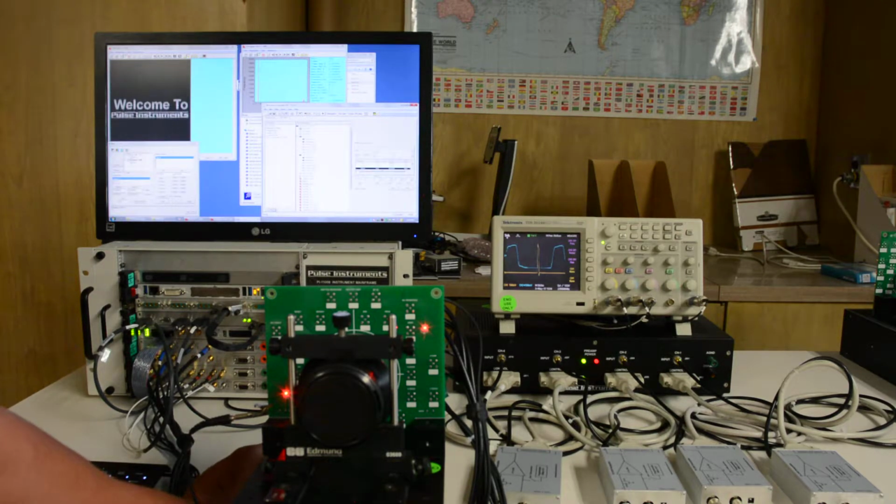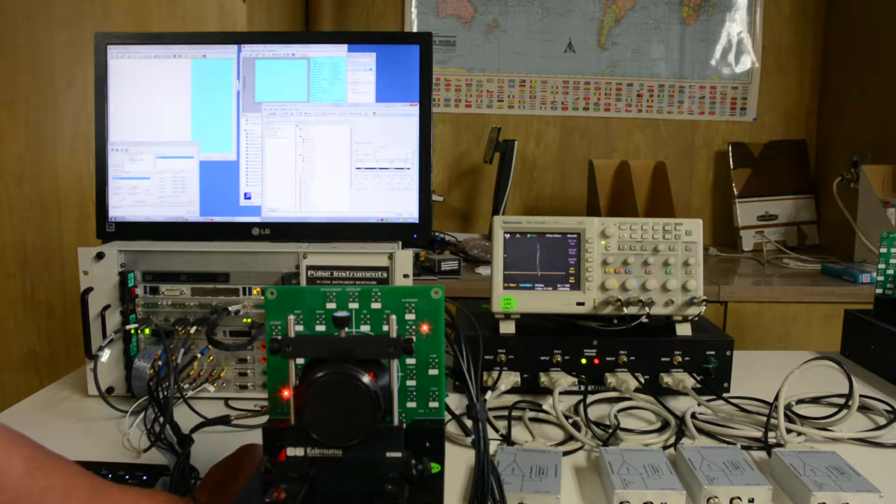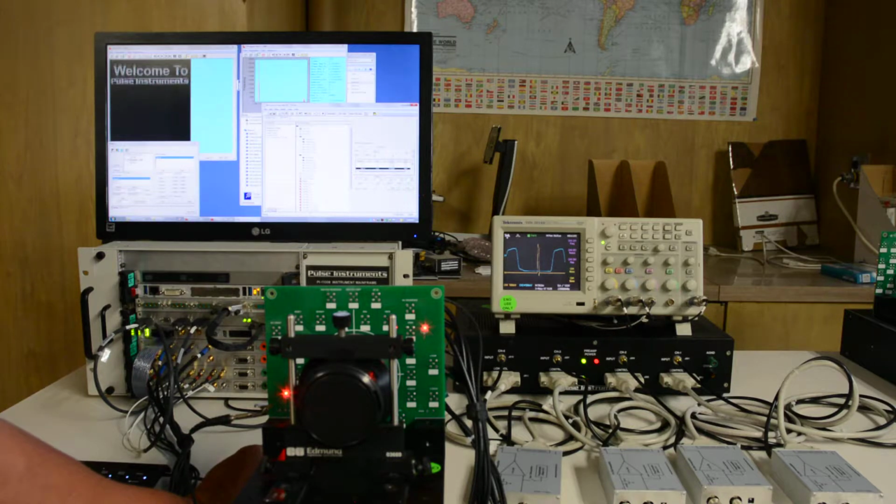And I also have control over the analog pre-processing of the signal. For example, I can sweep the DC offset into negative saturation or positive saturation, and I can adjust the gain. That's at a gain of 1, and I can increase this to saturating on both sides. I'll leave that back at 1.